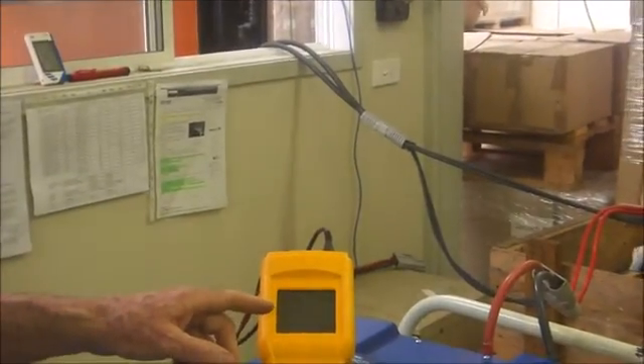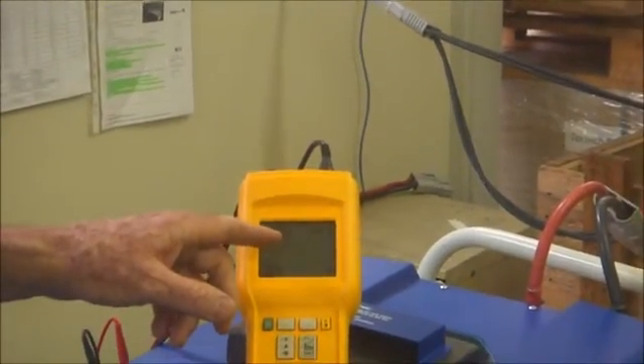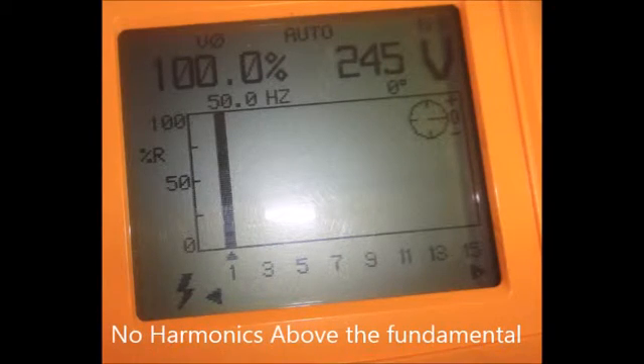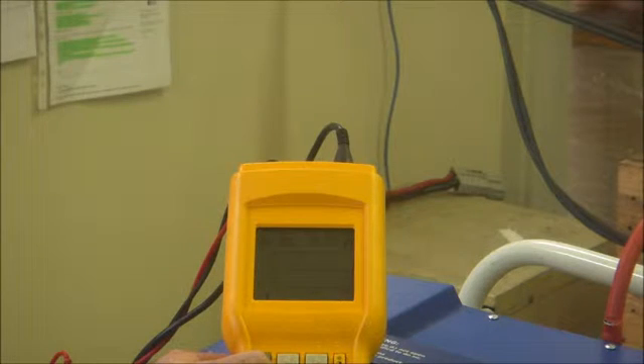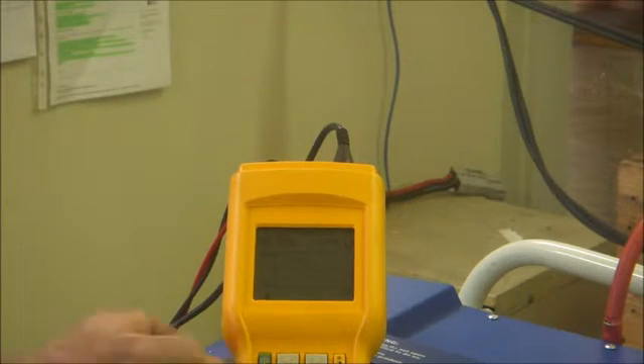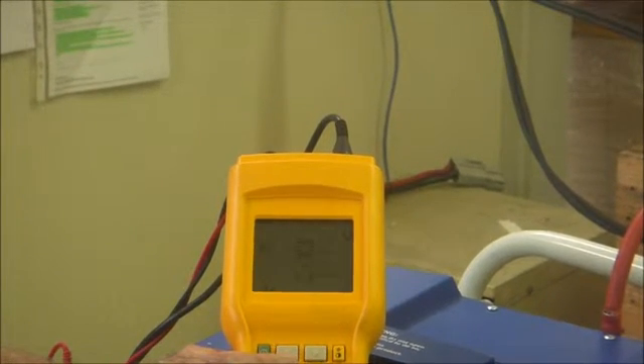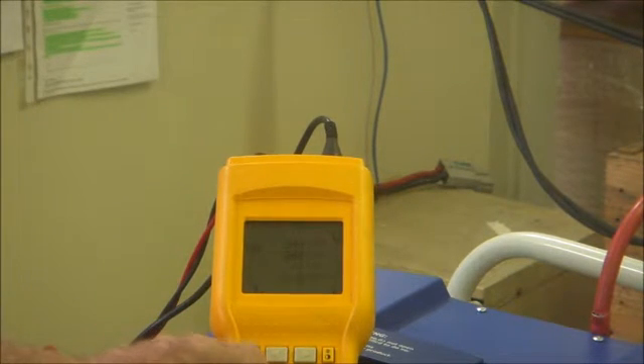So here we have a 50 Hertz waveform at 245 volts coming out. The fans are turning on. How much load have we got on now? We've got only a small load coming out. Nothing load. Okay, so here we are at no load. You can see the waveform is pretty clean. Let's have a look, we've got about 1.7% total harmonic distortion, 244 volts RMS, 342 volts peak coming out. Now, let's put some load on.